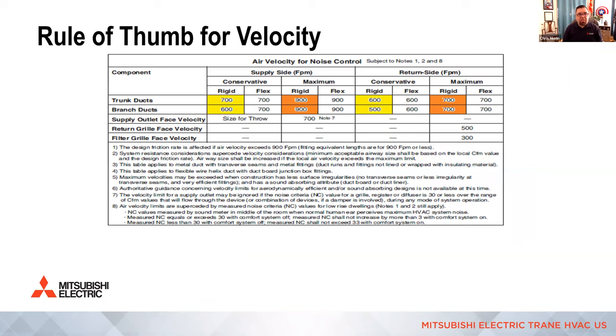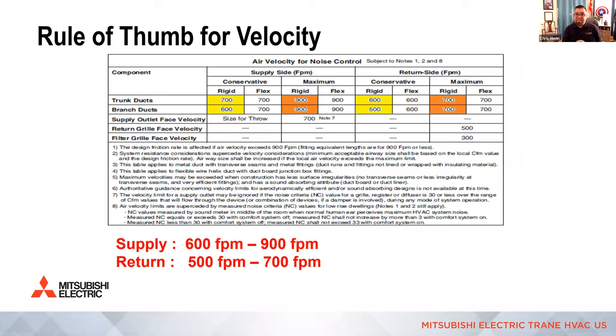And you can see this chart tells you for trunk and branch ducts, if you have on the supply, somewhere between 600 to 900 feet per minute is fine. Anything over 900 feet per minute is going to be too noisy and you want to make your duct larger to slow the air down. Anything below 600, you want to make the duct smaller to speed the air back up. And then of course, we want it a little bit quieter on the return because filters start to get dirty, ECM motors start to ramp up, and it's really easy for us to go past design, right? So we slow the air down a little bit more in the return. And that's typically 500 to 700 feet per minute when we're sizing returns. Okay, so those are the mins and maxes that you want to abide by.